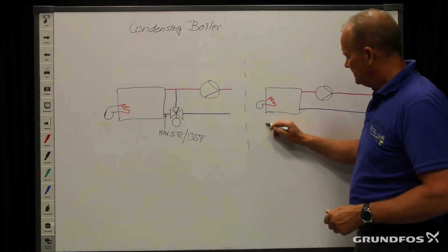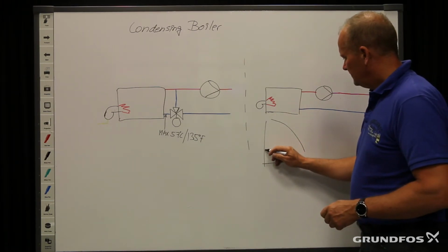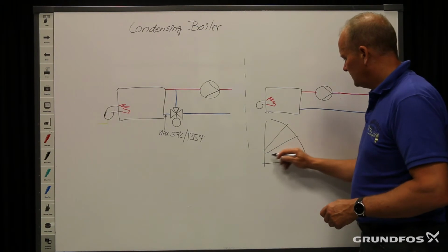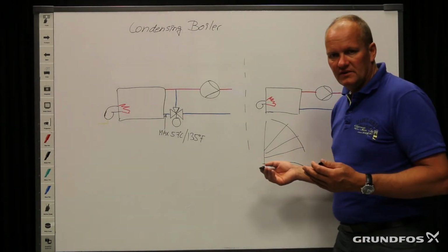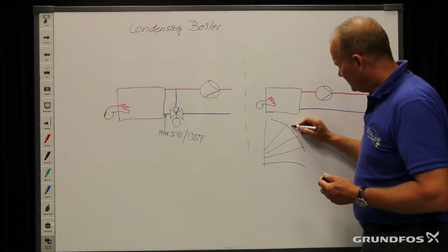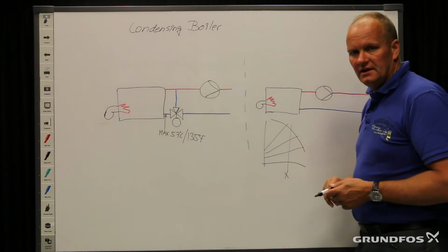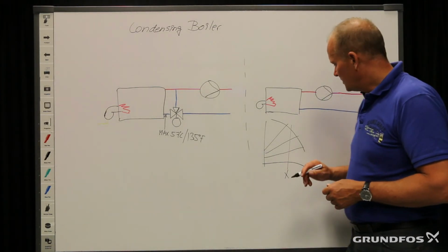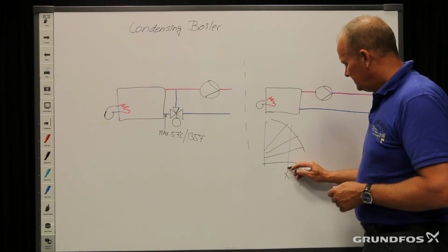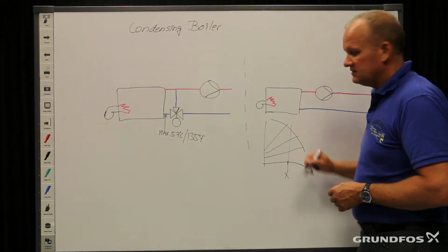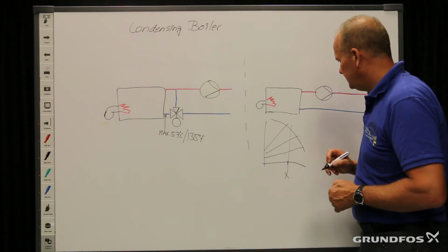choose the features. Maybe we have set the pump to operate on a certain level of proportional pressure, and then what we can do is that we can allow the flow limit function to work, and then secure that we will not exceed the specific design data for the system, which is illustrated by this vertical line here.